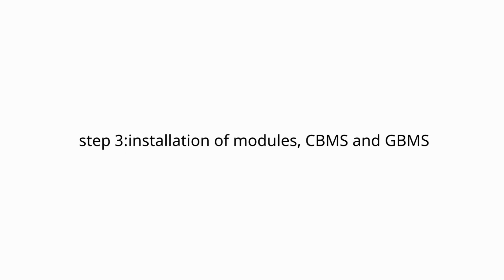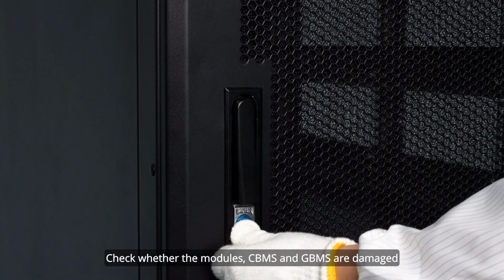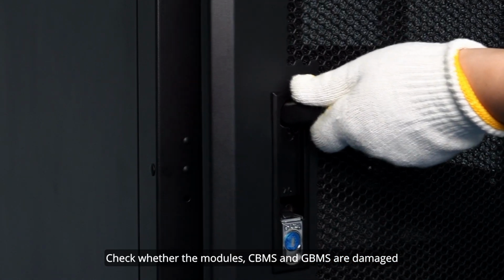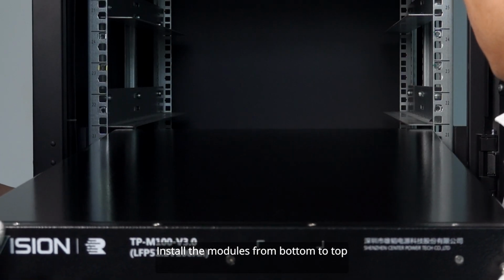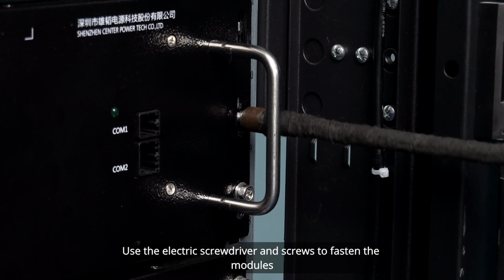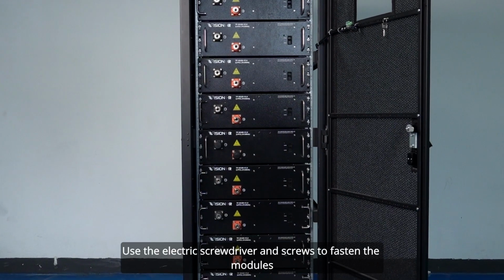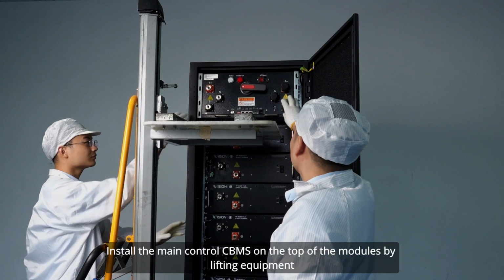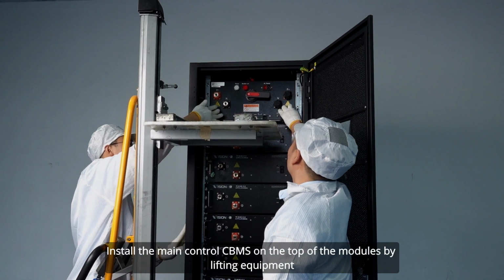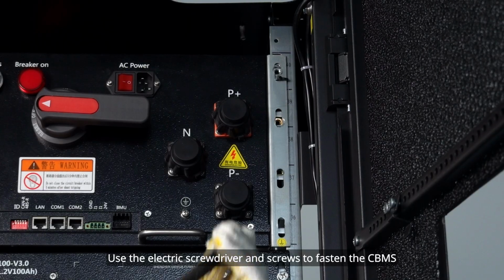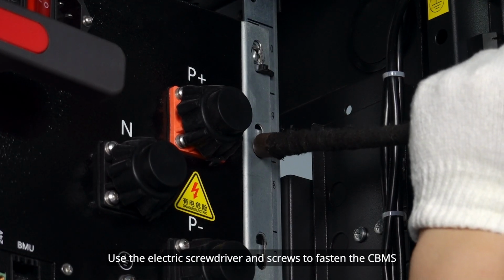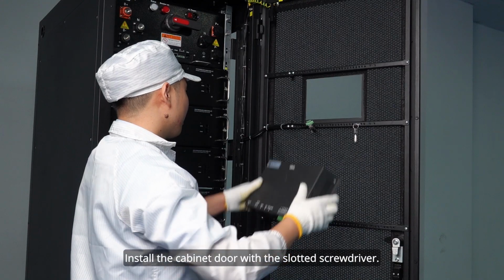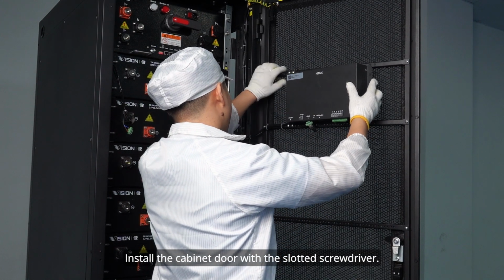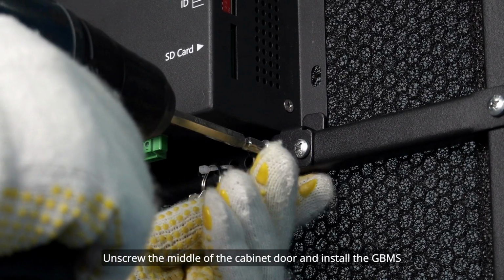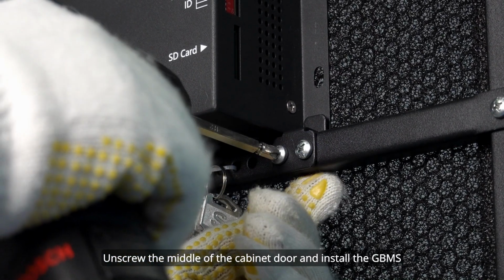Step 3. Installation of modules, CBMS and GBMS. Check whether the modules, CBMS and GBMS are damaged. Install the modules from bottom to top. Use the electric screwdriver and screws to fasten the modules. Install the main control CBMS on the top of the modules by lifting equipment. Use the electric screwdriver and screws to fasten the CBMS. Install the cabinet door with the slotted screwdriver. Unscrew the middle of the cabinet door and install the GBMS.